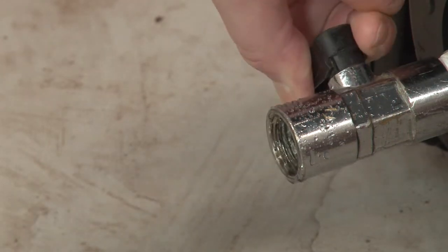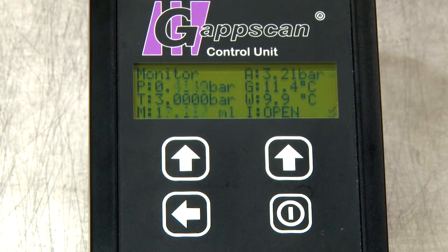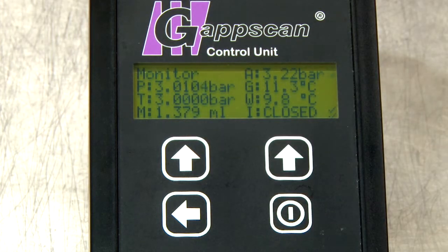Leave the valve in the closed position and the pressure will start to build until it reaches the target of 3 bar. The internal valve may be heard modulating the input supply. When the live variable pressure P and the target pressure T have stabilised to within 2 decimal places, you are ready to start the test. If P does not stabilise, it usually means that there is air in the system, so you would have to bleed more water through and start again.